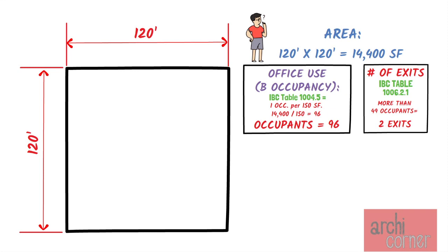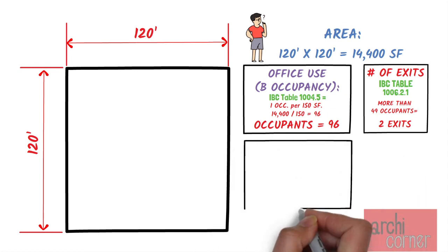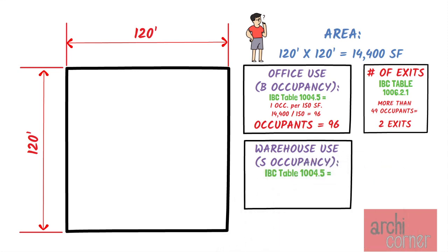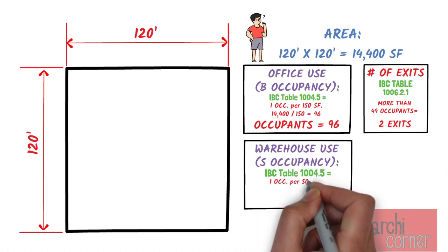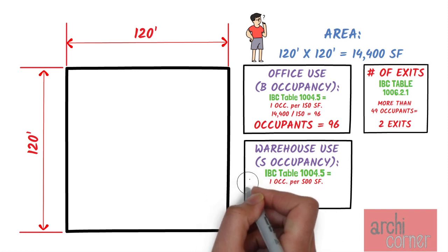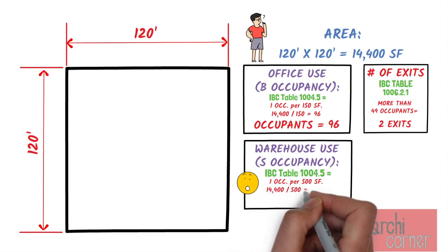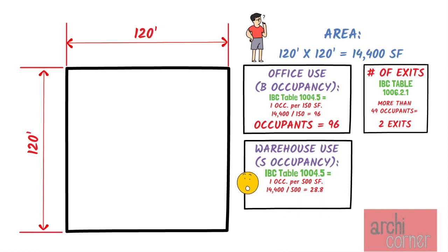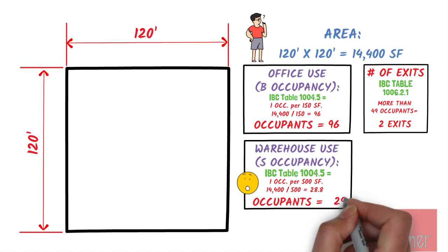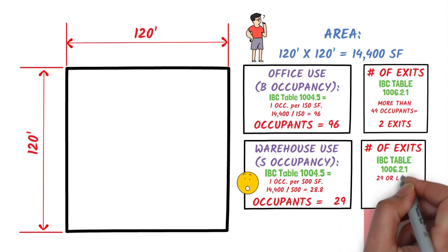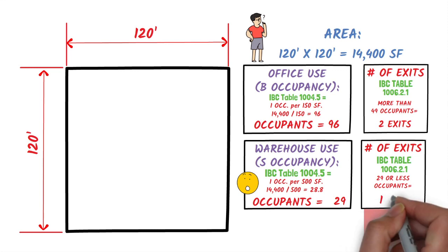However, occupant load alone doesn't always give you the right answer. If this exact same space was used for warehouse, the occupant load will change. The IBC requires the occupant load for warehouses to be determined at one occupant for every 500 square feet — a huge difference, cutting the occupant load to less than a third of office space. Doing the math: 14,400 divided by 500 equals 28.8, which rounds up to 29 occupants. Per IBC Table 1006.2.1, this space has 29 or fewer occupants and will therefore only require one exit if we base it solely on occupant load.